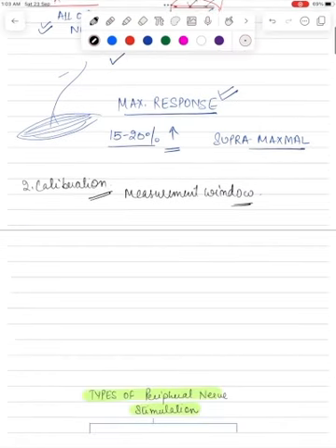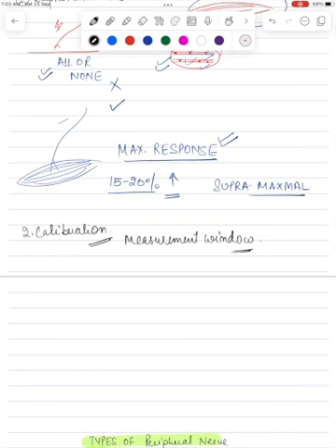Even if you have given a supramaximal stimulus, you might not get a response if the recorded response lies outside the measurement window of the measuring device. Therefore, calibration of the device is essential before using it. Calibration is most often done with a 1 Hertz single twitch stimulation.